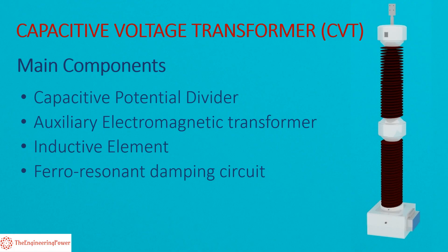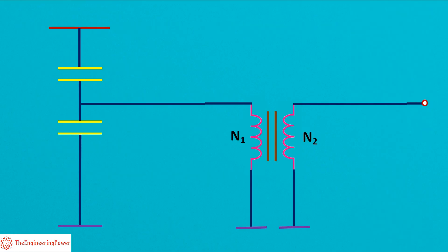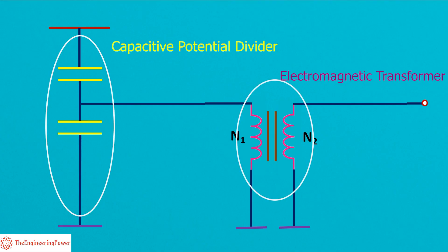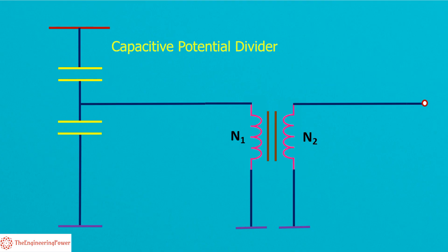Now we explain the working of CVT with the help of connection diagram. The extra high voltages are first stepped down using the capacitive potential divider. The output medium voltage is then further stepped down easily with the help of auxiliary electromagnetic transformer. The capacitive potential divider consists of a group of capacitors. The number of capacitors depend upon the voltage level. We consider the case of two capacitors. This potential divider circuit is connected to the main high voltage line whose voltage is to be measured or controlled.